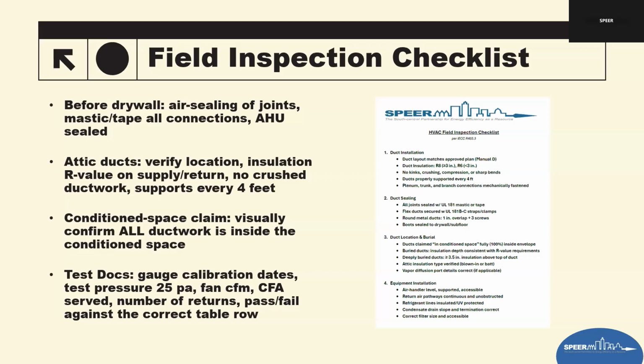And then testing documentation. Once duct leakage testing is complete, inspect the test report closely. Most reports may not say this, but each manufacturer of duct testing equipment now offers devices that can be connected to an electronic device that will print off a report once it's tested. That report should list a calibrated date for the gauges. The gauges must be calibrated annually in a field inspection calibration, and also calibrated every 2 to 4 years by the manufacturer. So the calibration date you normally see on the report will be the manufacturer's calibration date. When was it last verified by the manufacturer?